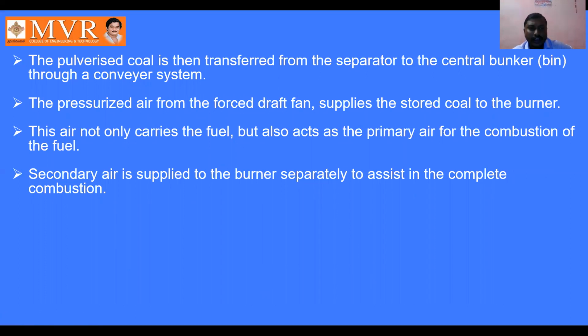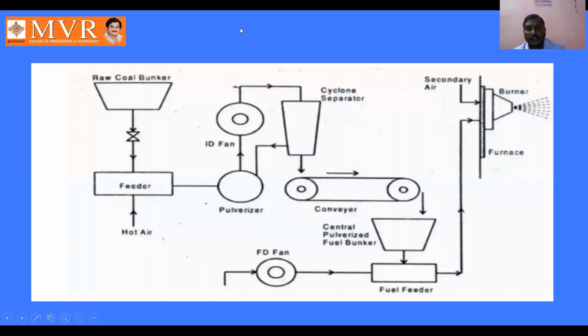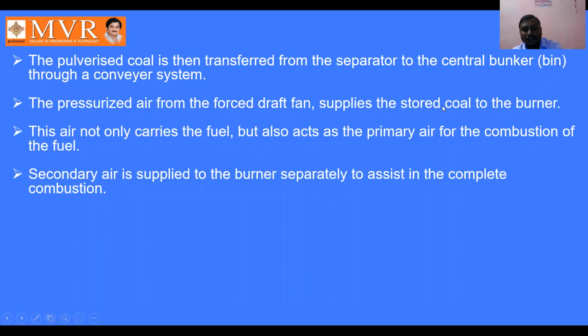This air not only carries the fuel but also acts as the primary air for the combustion of the fuel. For combustion of the fuel, this FD fan acts as the primary air. Secondary air is supplied to the burner separately to assist in the complete combustion. For completing the combustion process fully, the secondary air is very useful here for the burning purpose.